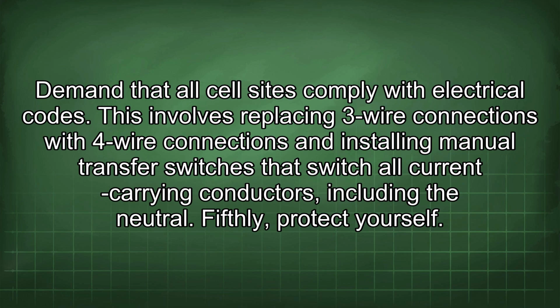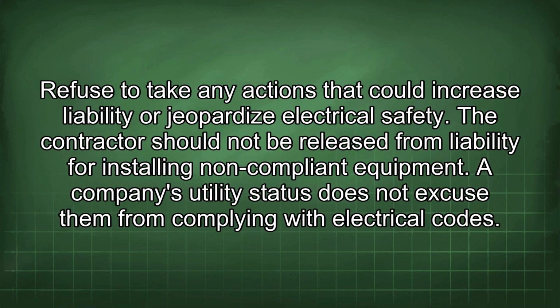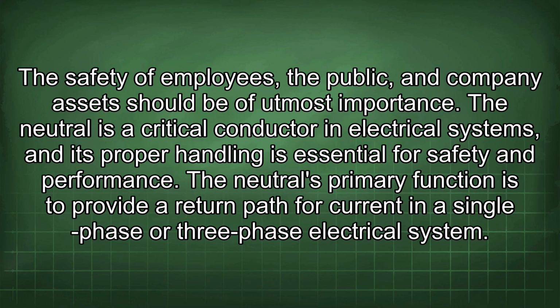Demand that all cell sites comply with electrical codes. This involves replacing 3-wire connections with 4-wire connections and installing manual transfer switches that switch all current-carrying conductors, including the neutral. Fifthly, protect yourself. Refuse to take any actions that could increase liability or jeopardize electrical safety. The contractor should not be released from liability for installing non-compliant equipment. A company's utility status does not excuse them from complying with electrical codes. The safety of employees, the public, and company assets should be of utmost importance.